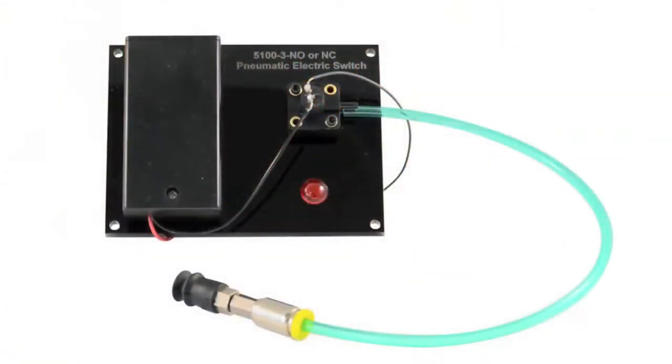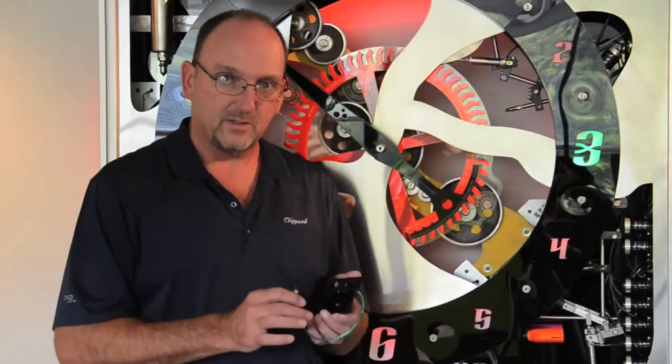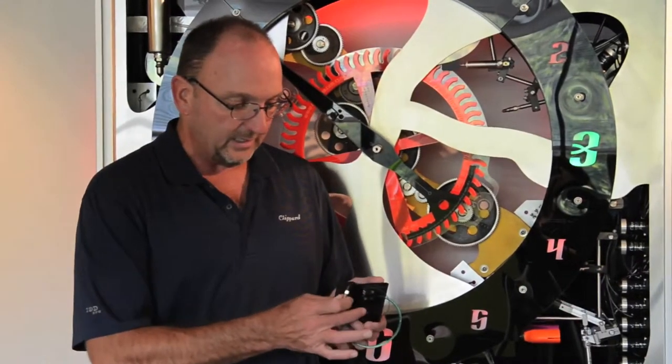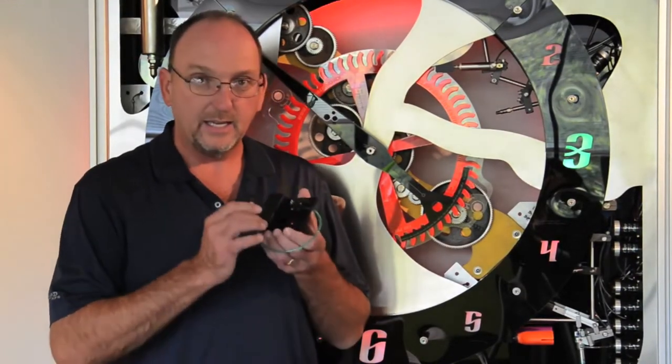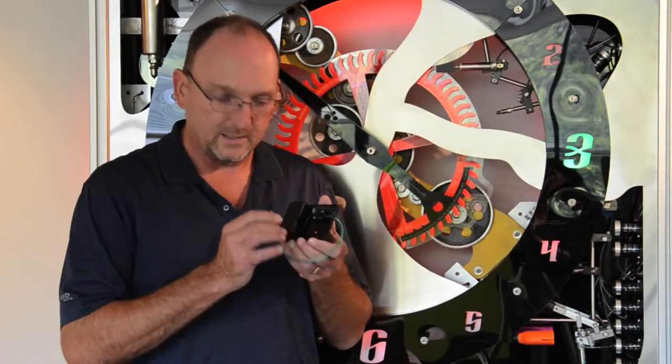The neat thing about this pneumatic electric switch is three inches of water column is the minimum operating pressure. This thing is very, very sensitive. I currently have it connected to the positive portion of the diaphragm, so as you can tell I can blow into this and the light will come on and complete the contact. This particular one is normally open contacts.